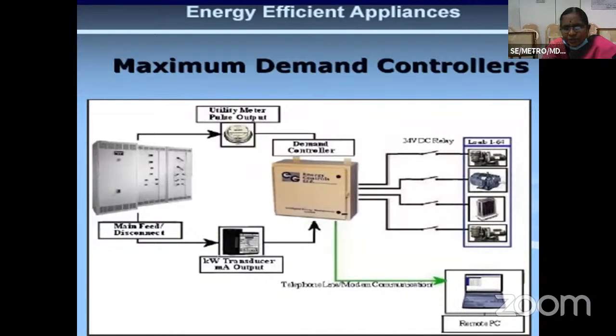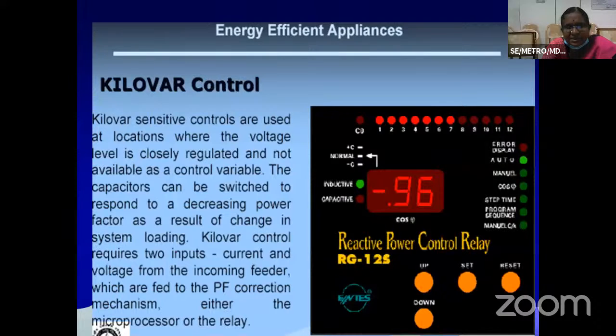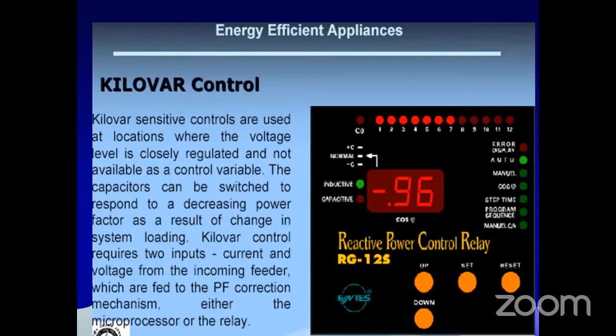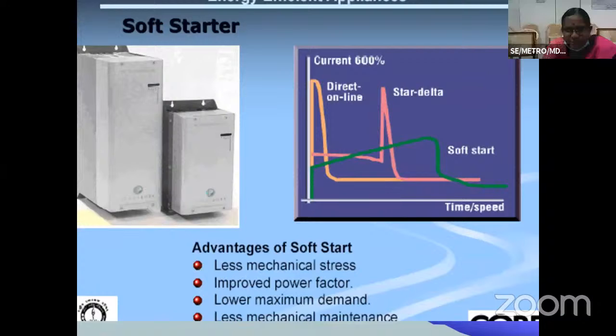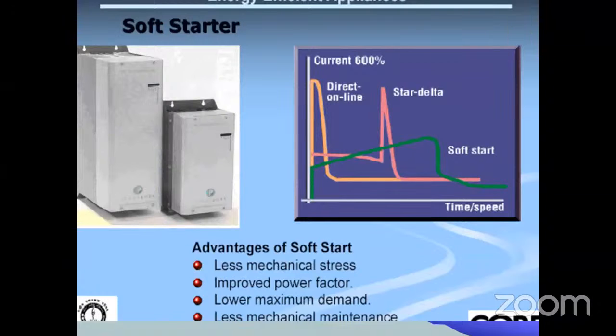This is the MD controller, because if you exceed the maximum demand, you will have to pay penalty. So this also can be installed to monitor your loads. This is kilovar control, automatic reactive power compensation. This can be installed in the industries at the load end. In TANGEDCO, we have provided this automatic reactive power compensation at all transformer ends. So this also could reduce the current I, whereby we could reduce the I squared R loss. As I've already said, instead of the direct starter, we can go in for soft starter.